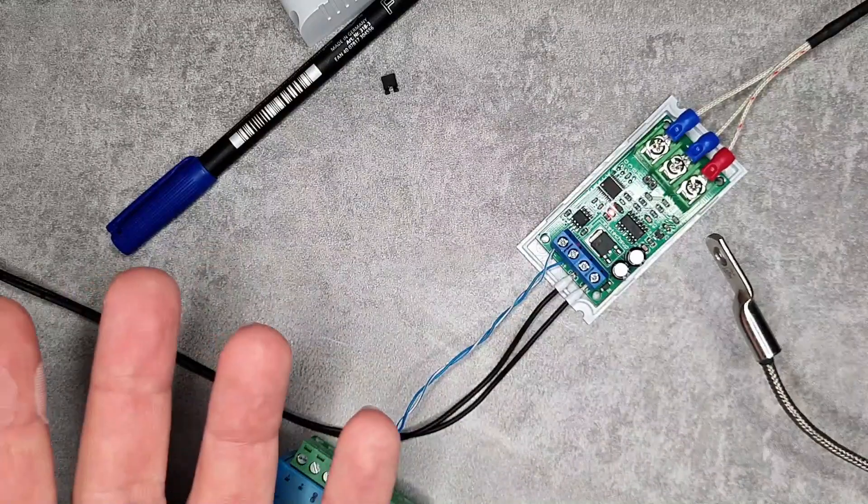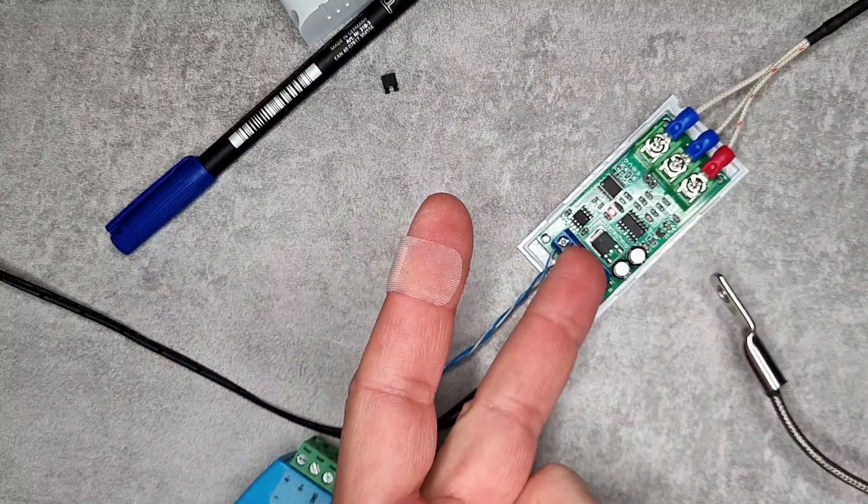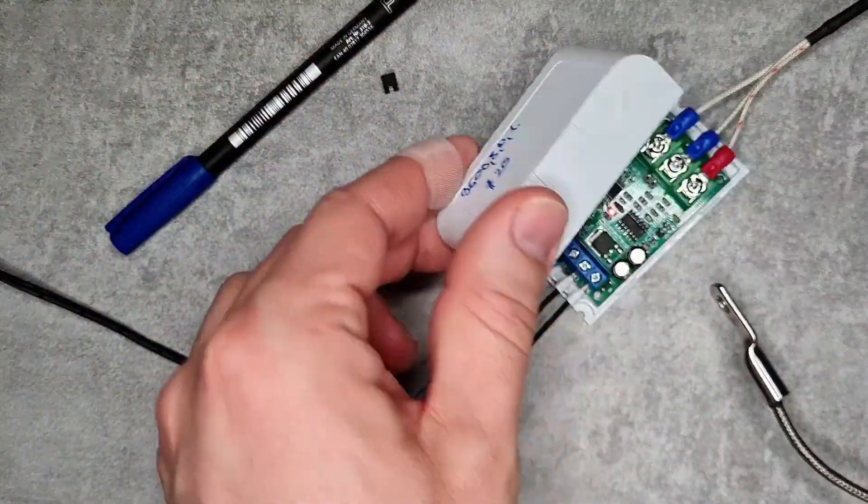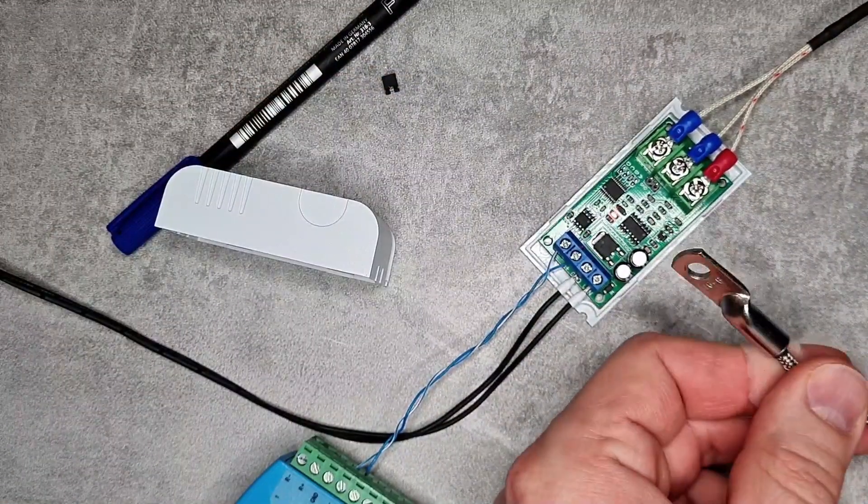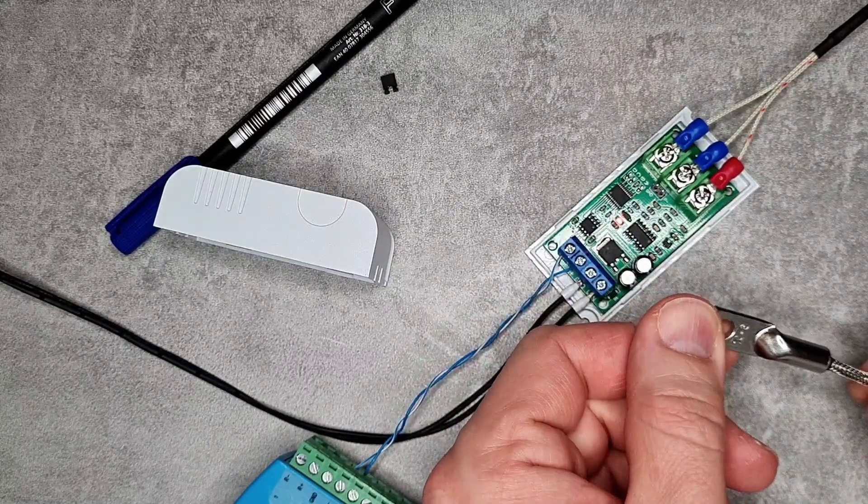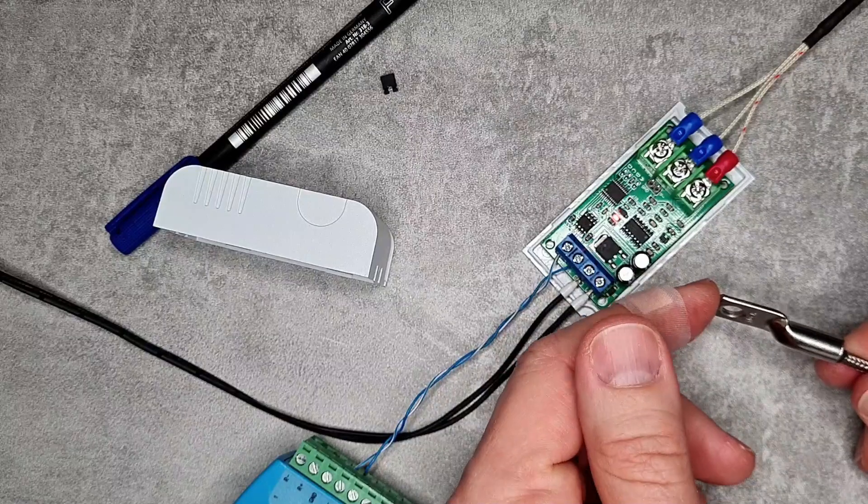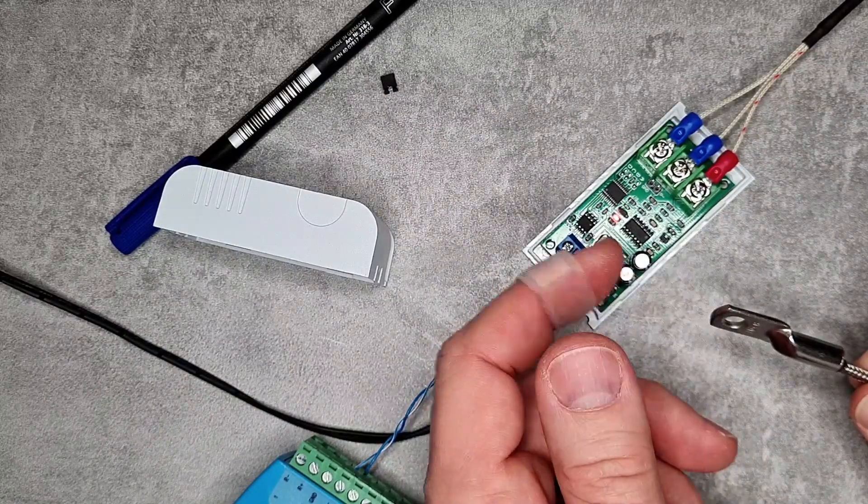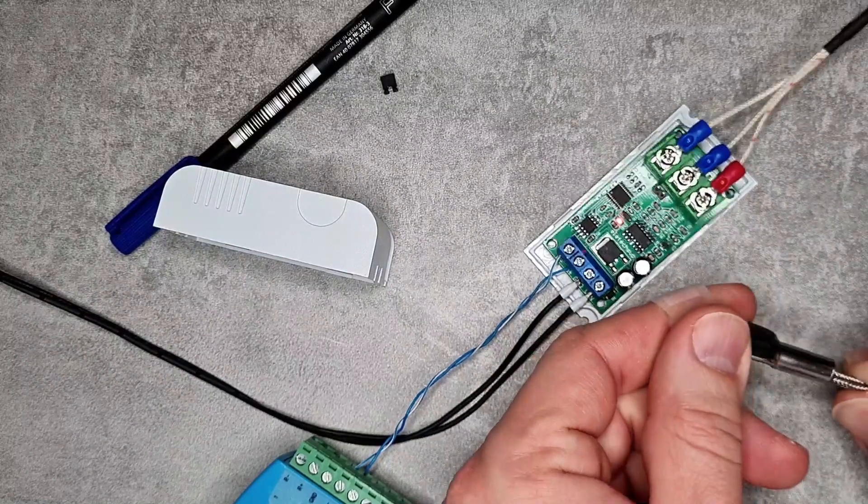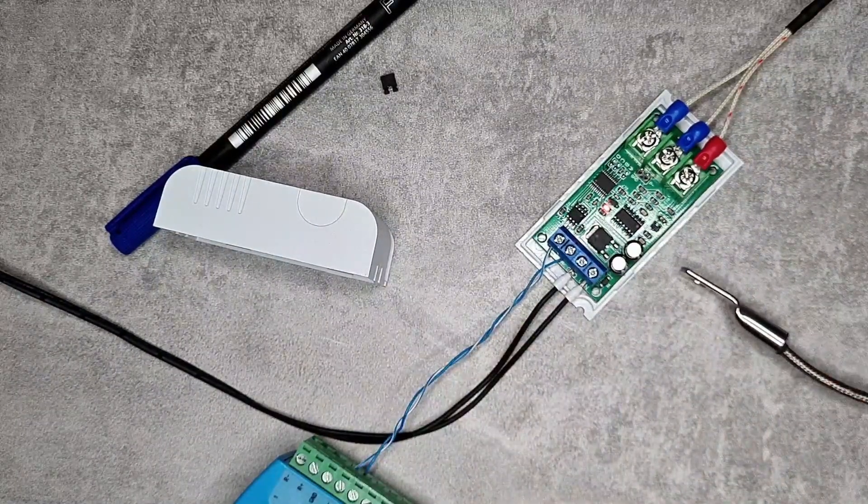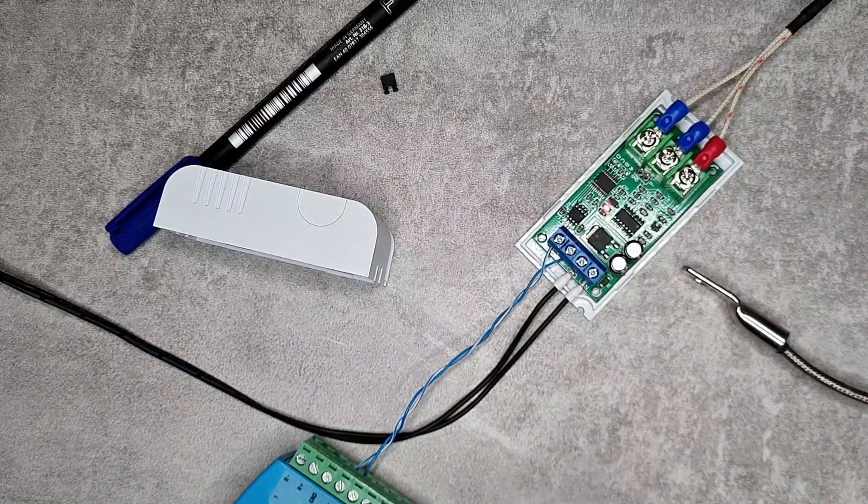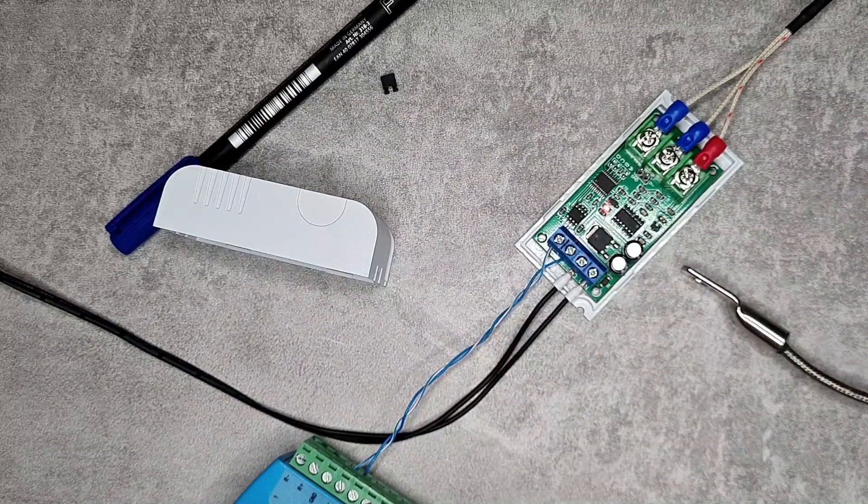What you buy is this sensor board. It also comes with an enclosure, a plastic enclosure, and it also comes with this PT100 temperature element which is terminated in this metal sleeve. If you're measuring temperature of like a copper or steel pipe, you can just clamp it to the pipe and it's going to measure the water temperature or the fluid temperature inside it. Everything works in Modbus so it's really easy to handle.